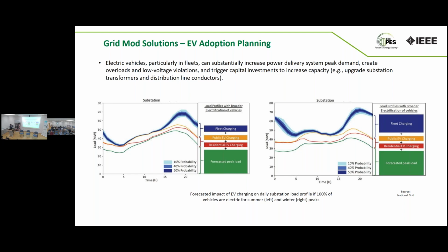So utilities are focusing on time-of-use rates to incentivize charging, for instance early in the morning. That's actually beneficial because now you're maximizing the utilization of your assets, increasing your load factor. But at the same time it can be a problem, because service transformers were designed expecting they'd operate close to maximum rating for a few hours a day, then cool off early in the morning, going through that heating and cooling cycle. If they're permanently loaded, that could affect their life cycle.